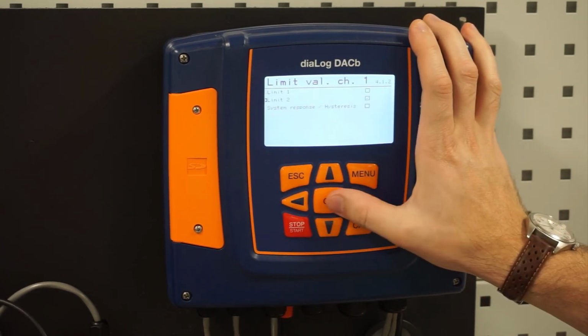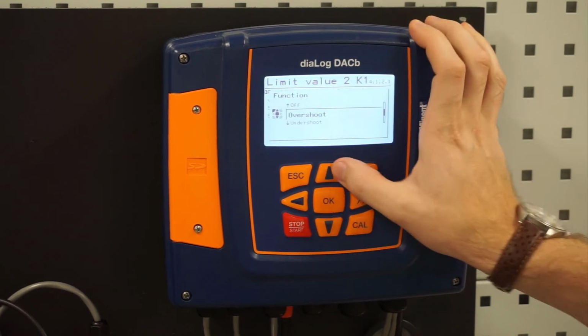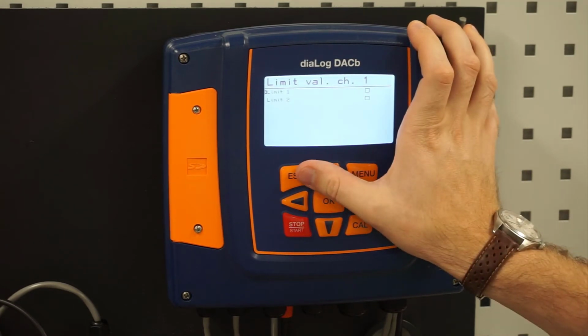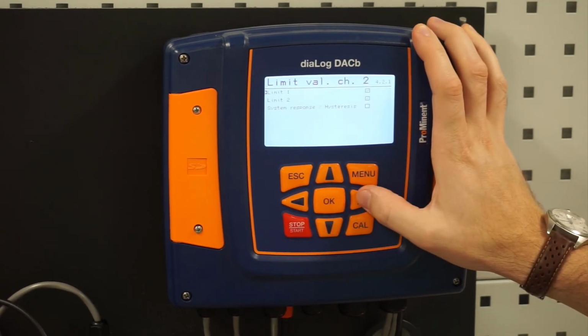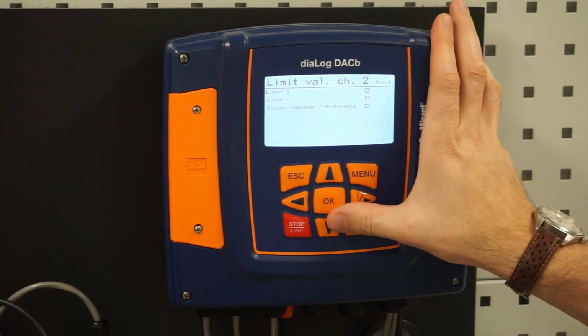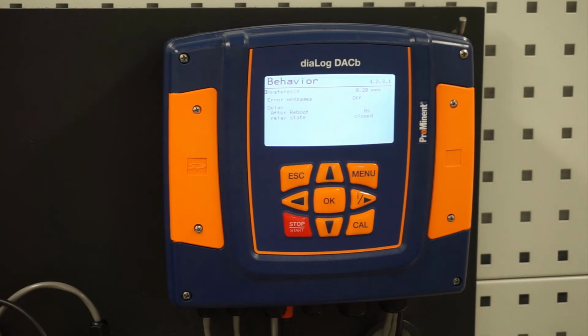Escape. I can set my high limit. Let's turn that off also. Hit escape, and escape again. Go to channel 2. One thing I'll show you before I shut these off is the hysteresis. The hysteresis is pretty important. It prevents relay chatter if we have this set up to a limit relay. Once we hit that limit, it determines how many ppm below that limit the value has to go before it turns back off. That prevents chattering if we're right on the limit. We can increase or decrease that, so if we're spending time around that limit, it doesn't chatter the relay.